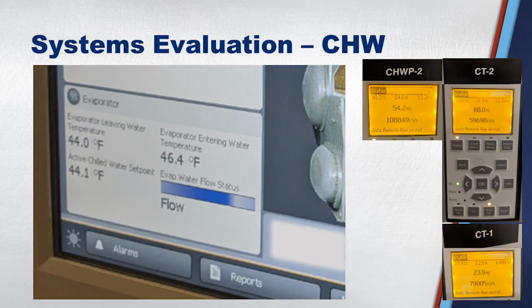You had 1 chiller running. I'm doing a 2.4 degree delta T. This chilled water pump is at 54.2 hertz, which is about 90%. So why am I flowing 90% of my water when I only have 2.4 degree delta T on a 12 degree delta T chiller? It doesn't add up.